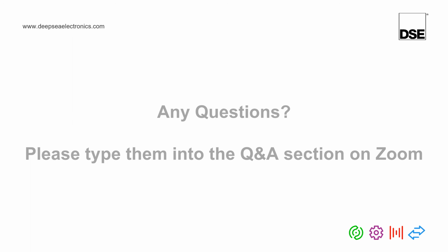Another question's just come in actually about 86 Mark 1s and Mark 2s, in reference to something called MSC compatibility. MSC compatibility does not need to be enabled when you're going from any version of Mark 1 86 to any version of Mark 2 86. However, you do need to enable MSC compatibility if you are using an 86 Mark 1 or Mark 2 with the older 75 and 5500 series products. So the MSC compatibility is only to make the 86 Mark 1 and Mark 2 work with the DSE 55 and 7500 series products.